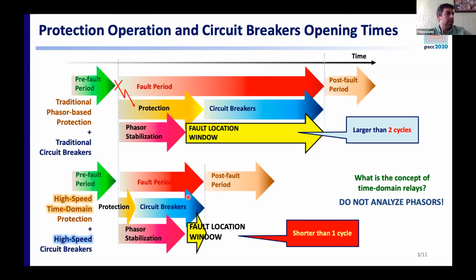Yeah, we have some impact of DC component on the estimated phasors. When we analyzed the evaluated case, we used some algorithms that are immune or mostly immune to the DC component, but that's a problem because even if I have 2 cycles, this DC component can still be present in the signal. We have some oscillation that will appear due to such a component, and this is a problem. That's why the estimated fault distance sometimes oscillates around the actual fault distance, and that's why we are proposing to consider the box plot representation when it is possible.